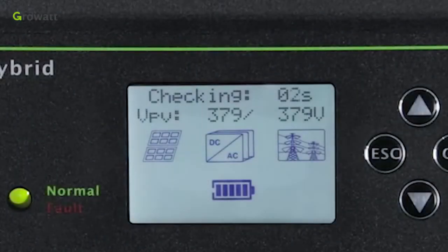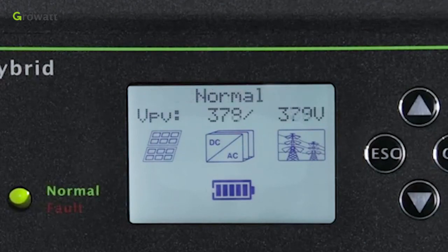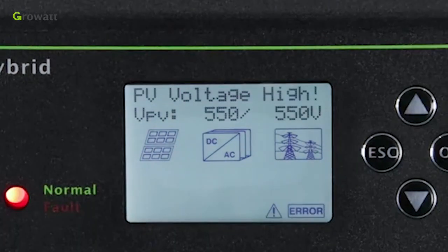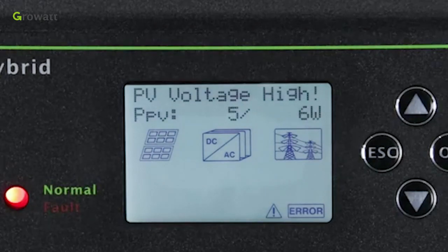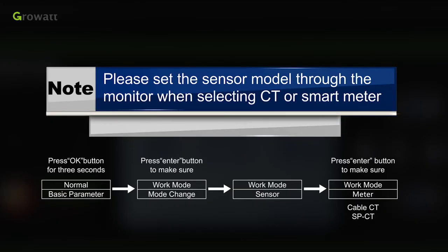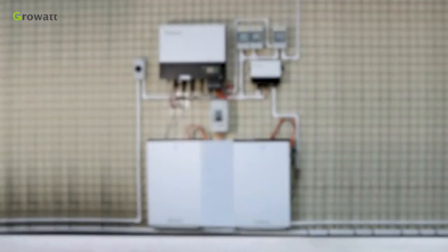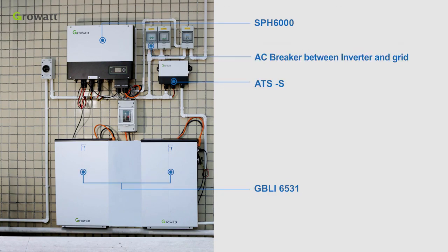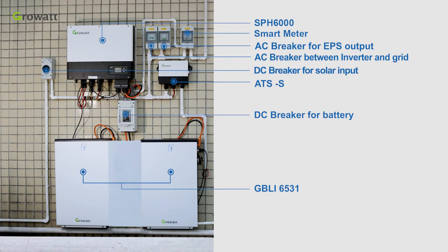After the system powers on, if PV, grid, and battery are all available, the system will work in normal mode. In normal mode, the screen shows 'normal' and the LED is green. If the SPH did not enter normal mode, especially if the LED is red, please contact Growatt Service Engineer for help. Please set the sensor model through the HMI when selecting CT or smart meter. The final energy storage system includes: SPH6000, GBLI6531, ATS, AC breaker between inverter and grid, AC breaker for EPS output, smart meter, DC breaker for battery, and DC breaker for solar input. Thank you.